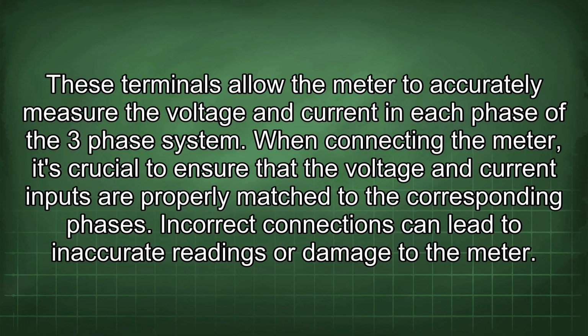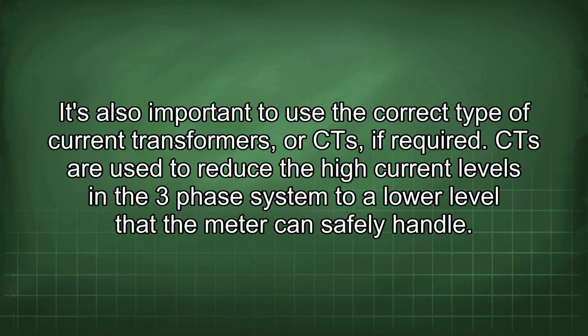When connecting the meter, it's crucial to ensure that the voltage and current inputs are properly matched to the corresponding phases. Incorrect connections can lead to inaccurate readings or damage to the meter. It's also important to use the correct type of current transformers, or CTs, if required.